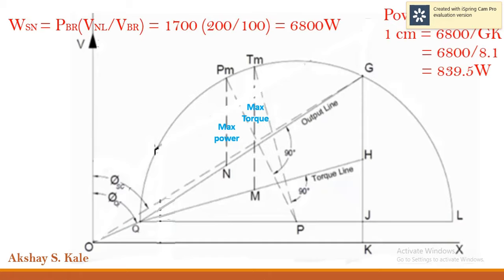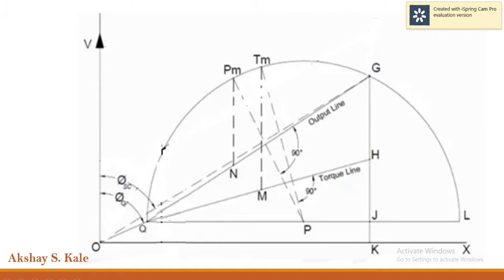Now it's time to calculate the power scale. We have already found WSN as 6800 Watts. First, measure the length of line GK, which comes out to be 8.1 cm. After dividing WSN by the length of GK, we get the power scale as 1 cm equals 839.5 Watts. Our induction motor in the example is 5 HP. Converting: 1 HP = 745.7 Watts, so 5 HP = 3728.5 Watts. Dividing 3728.5 by 839.5, we get 4.44 cm.